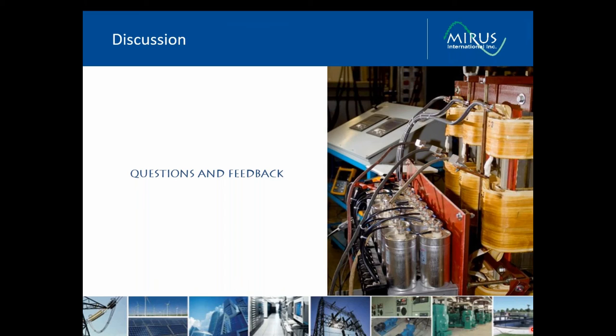Absolutely. That practice is a very dangerous one and certainly could be a very, very expensive one. One of the examples that I gave was those 8 IMR vessels, or offshore service vessels, that originally were designed with active front-end propulsion systems. The supplier of the AFE drives could not get them to work. The only solution was ultimately to strip them out and replace them. Of course, that delayed the project significantly and definitely cost the supplier of the active front-end drives a lot of money.